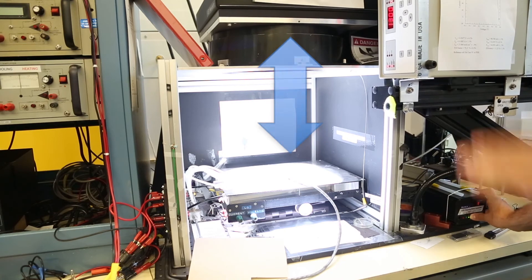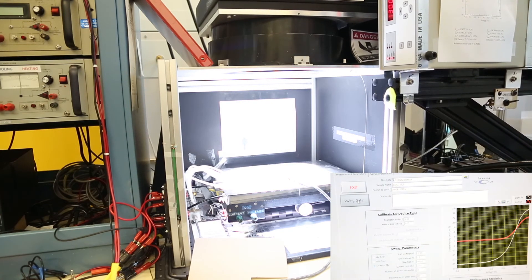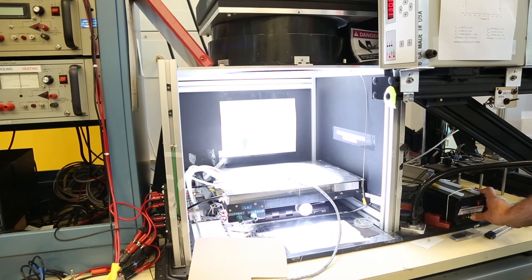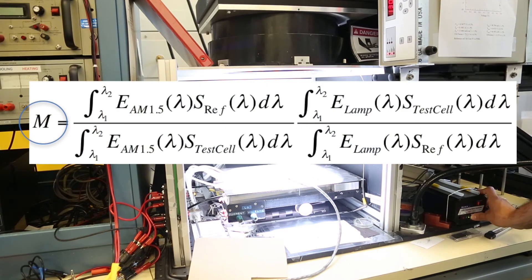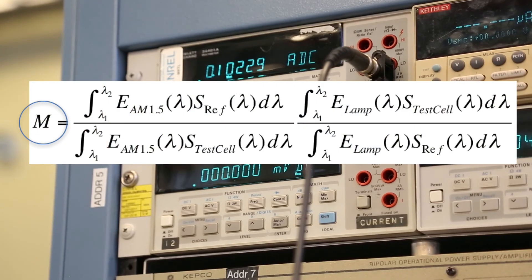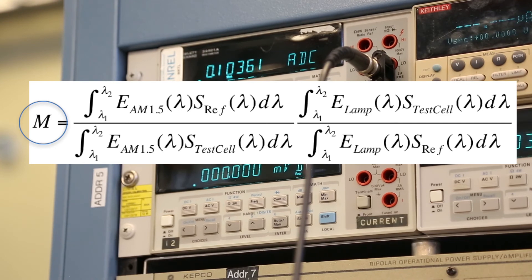Now we can measure the short circuit current of the test cell using the light source you have. Then we calculate the spectral mismatch factor M by plugging the values from the previous step as shown in the equation here. Ideally, M should be as close to unity as possible.